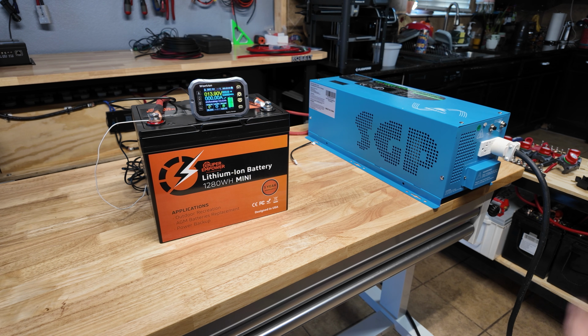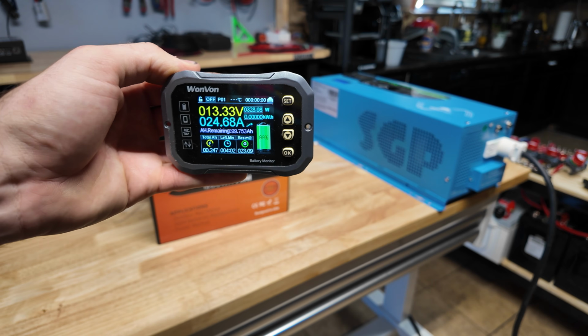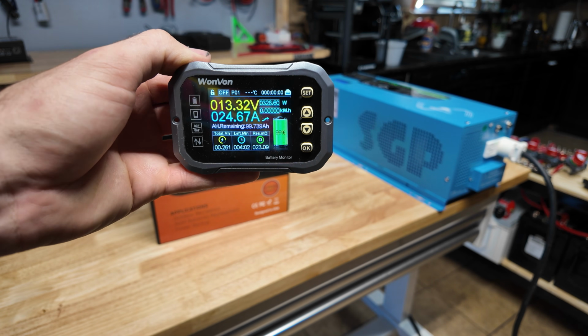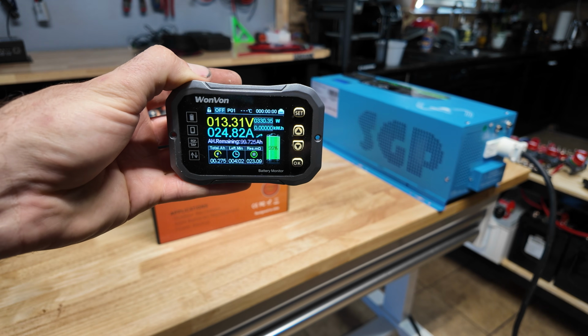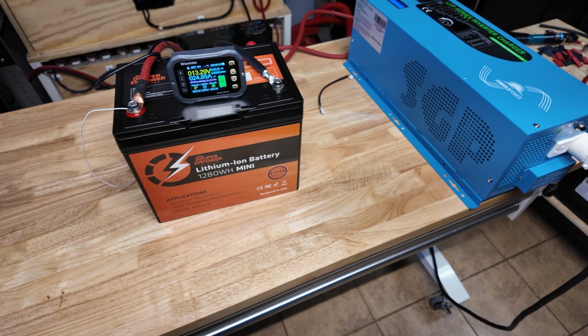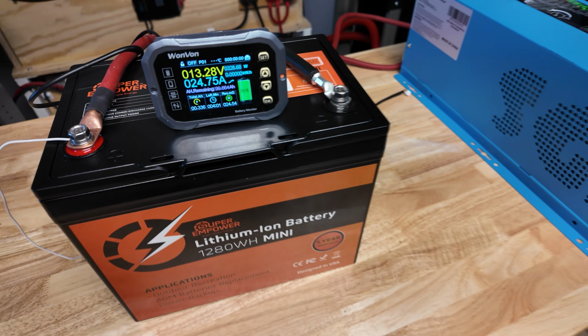Now we're going to put a 20 amp load on the battery, for our 0.2 C rate discharge. I'm using a charge verter to put the load on, and I can't get it any lower than 24, so we're just going to run the test at 24 amps. It should take about 5 hours to complete, so once it's over, I'll show you guys the results.